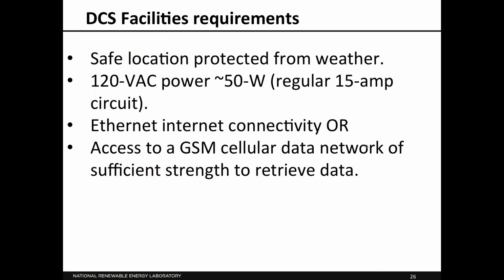So facility requirements for the DCS: we need it to be in a safe location, protected from the weather, vandalism, things like this. It should be behind a fence so it's not going to get broken or stolen. We need 120 volt power, a regular 15 amp circuit. The DCS should only consume about 50 watts. We will need access to either an RJ45 connection to get to the internet so the data can come back to NREL, which is our preferred option, but failing that, the systems will come with a cell modem, and as long as we can grab a GSM cell network with sufficient strength, that should be okay to grab data as well. So we need one of those too.